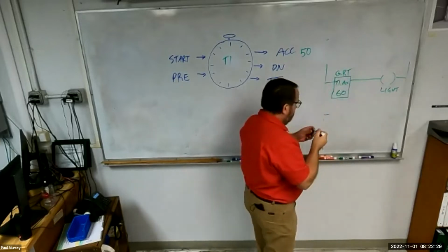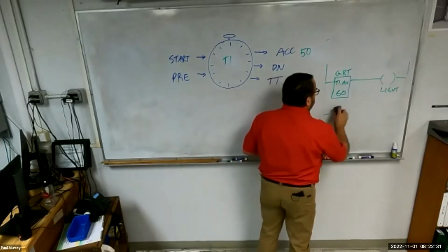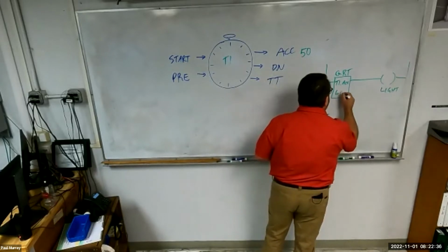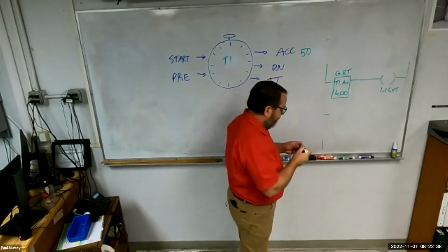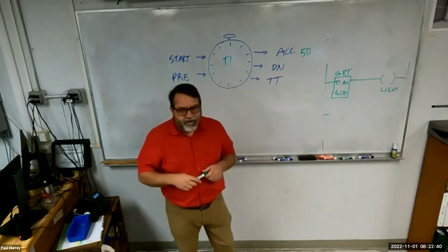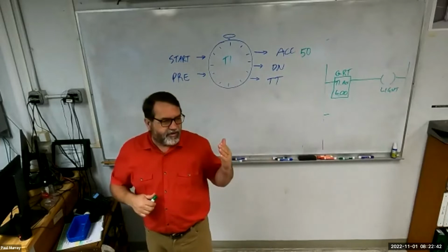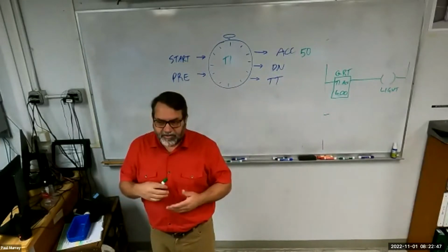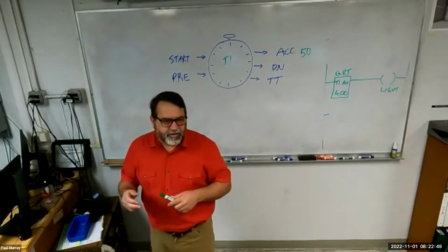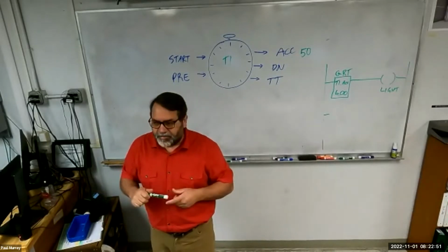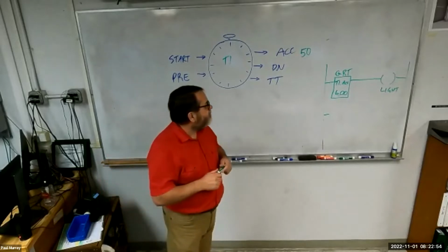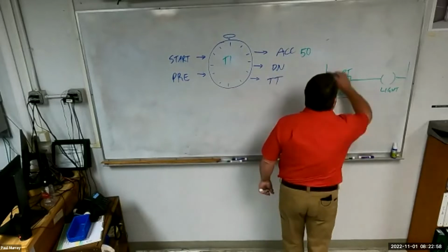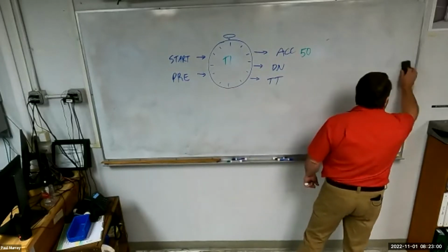I could use a greater than command, and maybe I'd put 600. So when my cumulative time gets above 600 minutes, I get a signal that tells me I have to go and grease the pump or do something to the pump. So I can use that kind of information. Anyway, that's real handy.